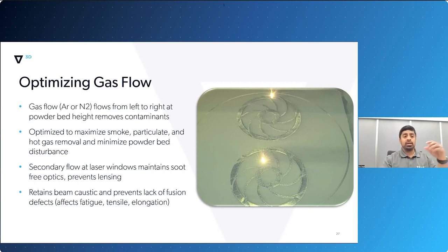Another thing that's a little unique is we found that through legacy systems, the optical window tends to get a lot of soot and condensate buildup and just gets dirty. So we've designed our machine architecture to have a slight positive flow at the optics window, which ensures none of that stuff gets carried into the window and contaminates it.